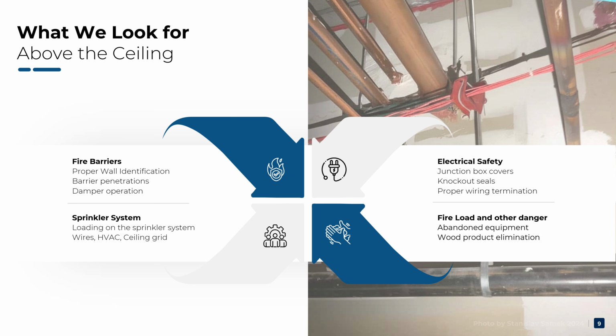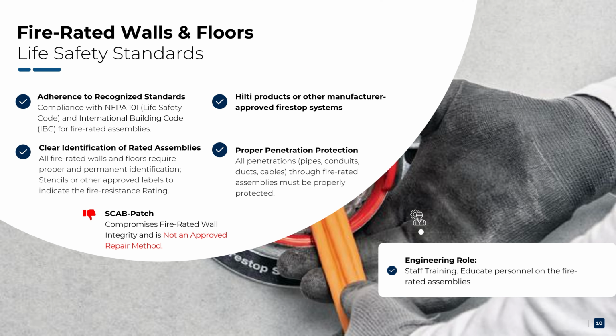Even something as seemingly minor as abandoned equipment from previous construction may have impact on the safety. So it's more than just is the ceiling clean. Exactly. It's about maintaining the integrity of the building's fire and life safety systems. Above the ceiling, we also watch for storage violations, blocked access to fire dampers, or improper materials that could increase fire load. Each finding tells us something about the overall risk and helps us prioritize repairs and ILSMs. Makes sense. It's really a peek into the building's hidden safety mechanisms. That's right. And in the next part, we can go through some of the most common deficiencies we find above the ceiling and why they matter for both safety and compliance.